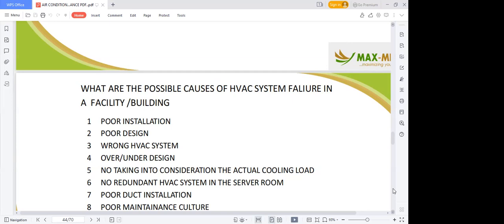Not taking into consideration the actual cooling load. When you need to design for a place, most especially a stadium and the rest, you need to know the actual cooling required for the space. There are software packages you can use to do that, and there's a rule of thumb you can also use. So you can use 0.18 kilowatts per square meter. Those of us writing, 0.18 kilowatts per square meter.